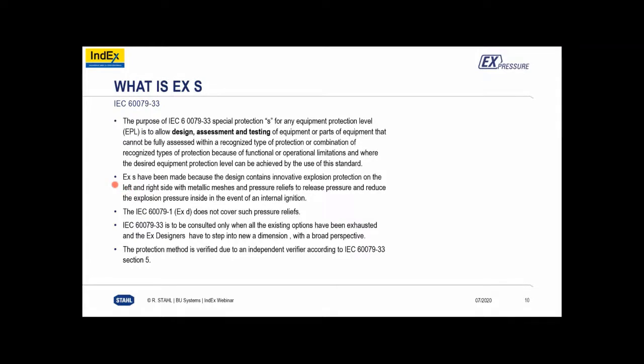And specifically, EXS has been made so that it allows for these unique innovations. The design contains innovative explosion protection on the left and right hand side with the metallic mesh and the pressure reliefs to release pressure and reduce the overall explosion inside in the event of an internal ignition. Now, 60079-1 EXD does not cover the explosion reliefs, the vents. Those are covered under -33. And -33 is to be consulted when all existing options have been exhausted and the EXD designers have to come up with new dimensions or a new protection method. So Stahl came up with ExPressure.